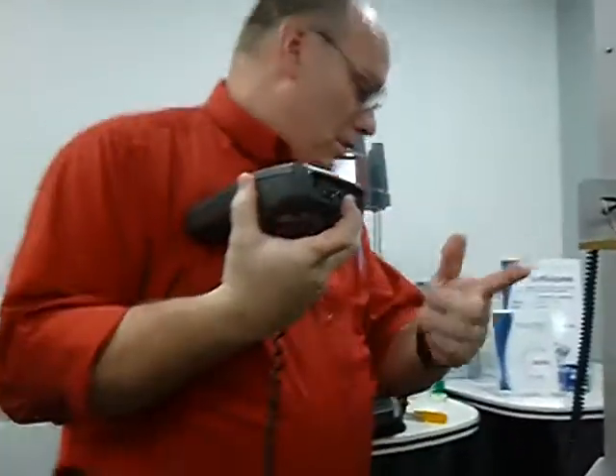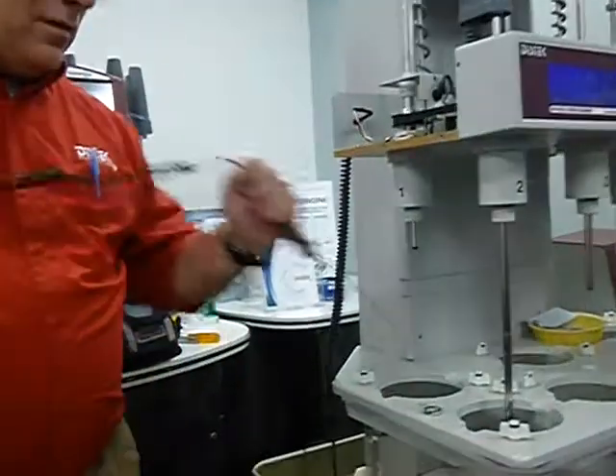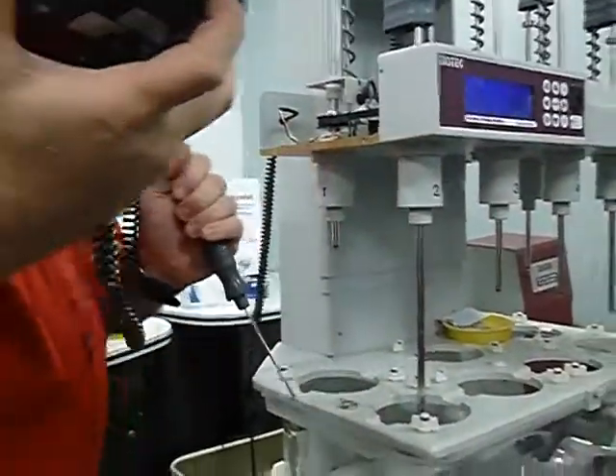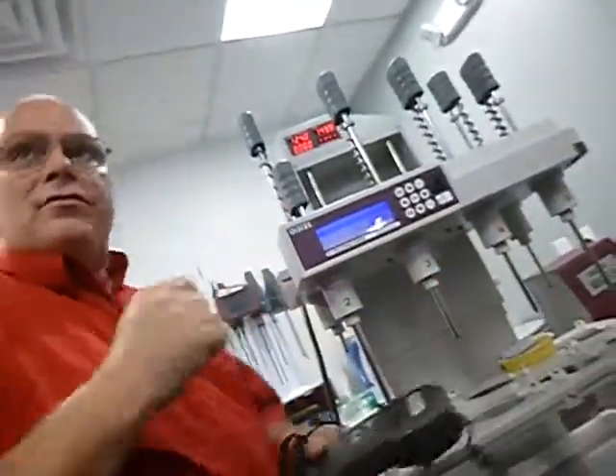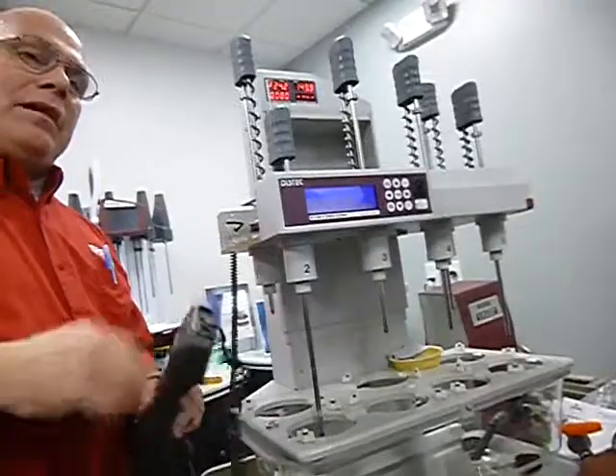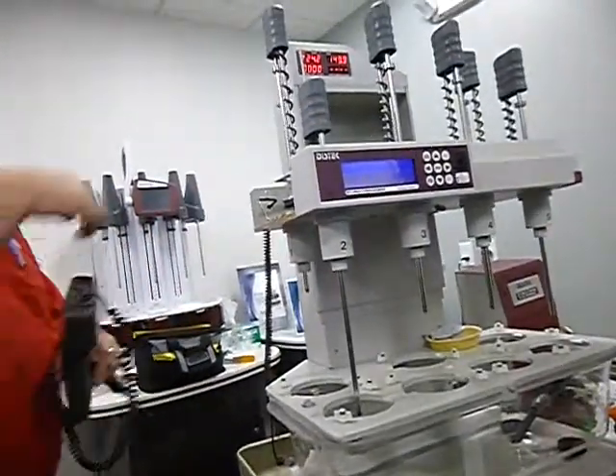to this and hook it up to the unit down here and use this to test each one of the positions and do the calibration on it. Or you could use this still without hooking a cable up or any thermometer and simply use reference. That's typically how I do it. It's typically how our technicians do it. I don't want to be bothered with hooking up the cable and having to worry about that.